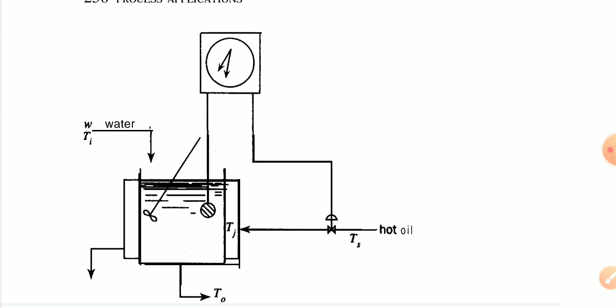This control system is satisfactory for controlling the kettle temperature. However, if the temperature of the oil supply should drop, the kettle temperature can undergo a large excursion from the set point before control is again established. The reason for this is the controller does not take corrective action until the effect of the drop in oil supply temperature is felt.